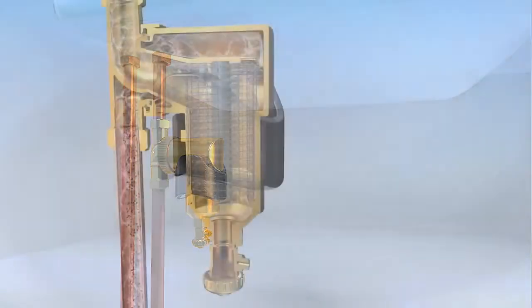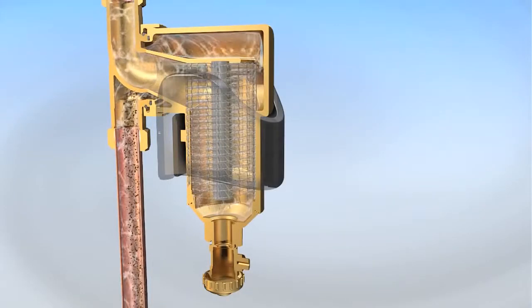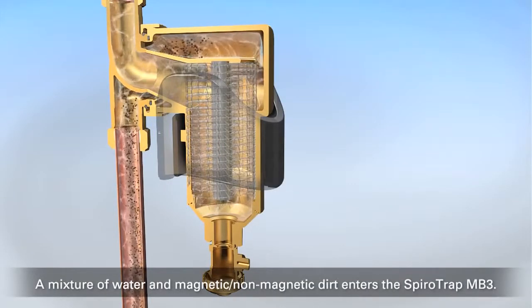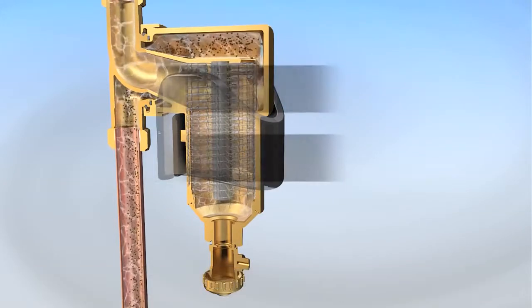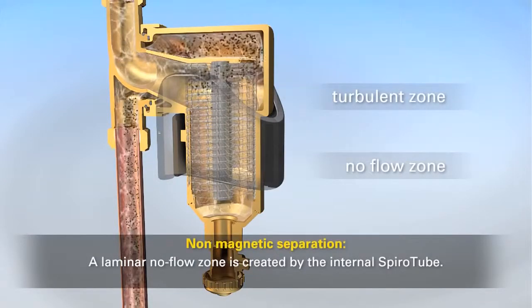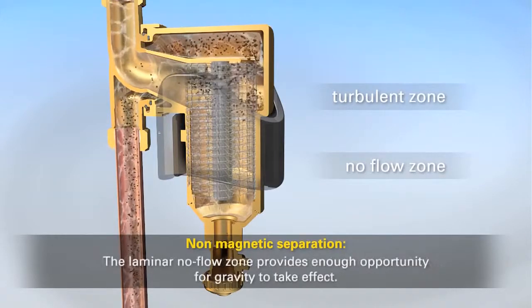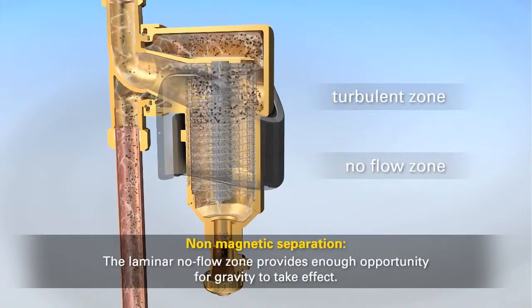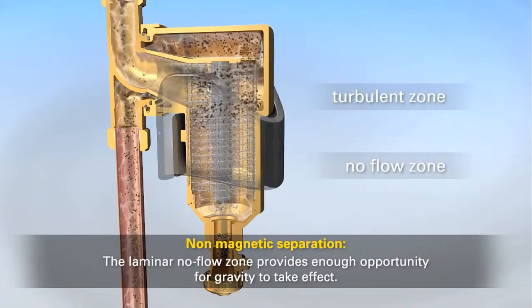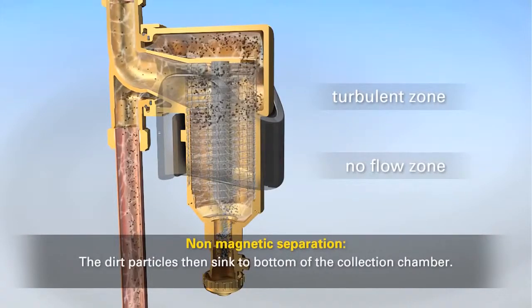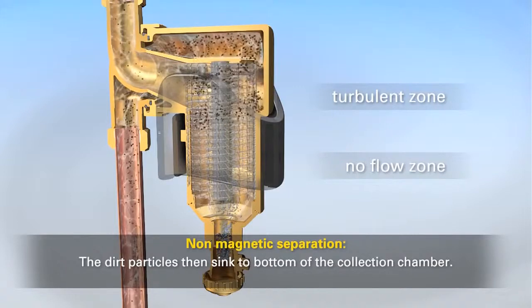The system water carries magnetic and non-magnetic dirt particles through the SpiroTrap MB3. A laminar no-flow zone is then created by the unit's internal SpiroTube, which provides enough opportunity for gravity to take effect. The dirt particles then sink to the bottom of the collection chamber.